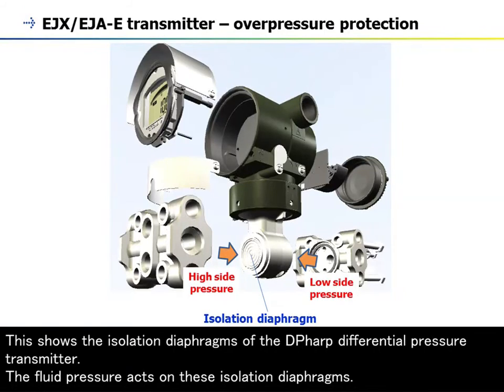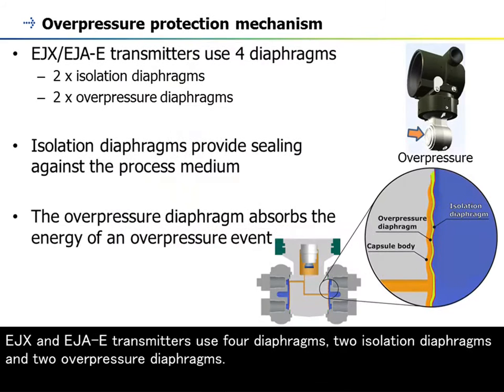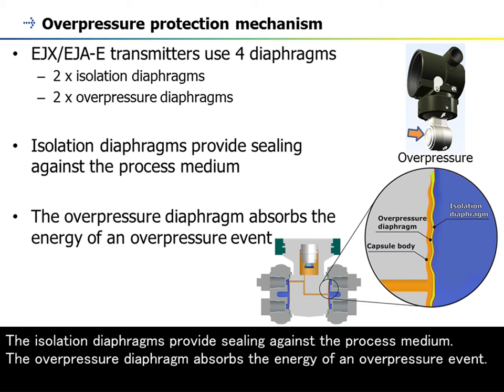This shows the isolation diaphragms of the DP-HARP differential pressure transmitter. The fluid pressure acts on these isolation diaphragms. EJX and EJAE transmitters use four diaphragms: two isolation diaphragms and two overpressure diaphragms. The isolation diaphragms provide sealing against the process medium, while the overpressure diaphragm absorbs the energy of an overpressure event.